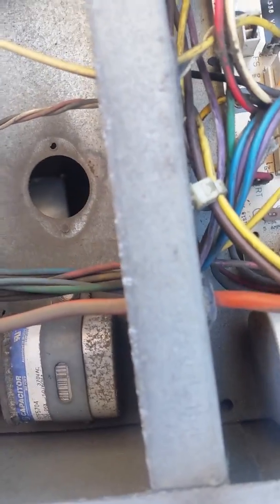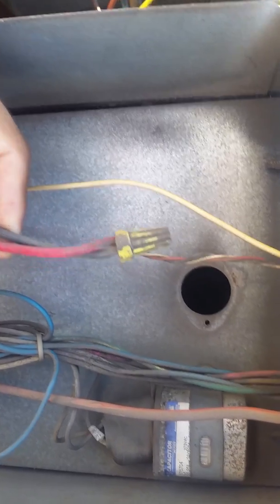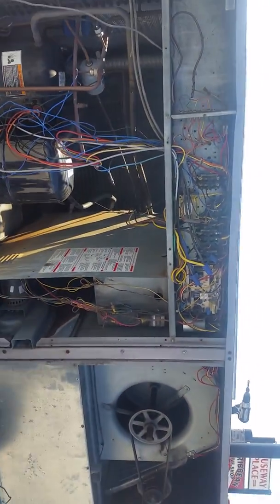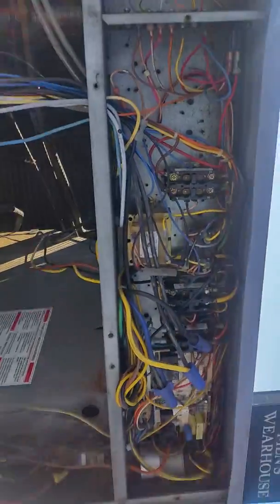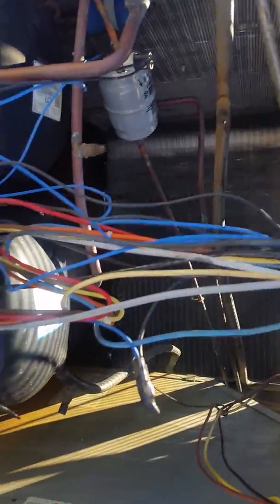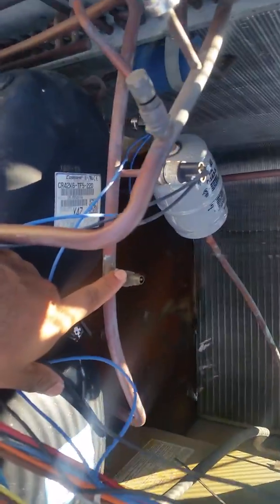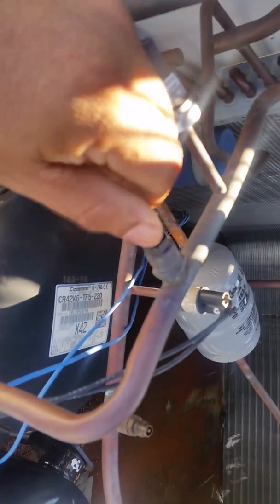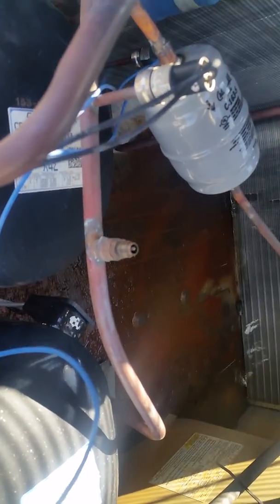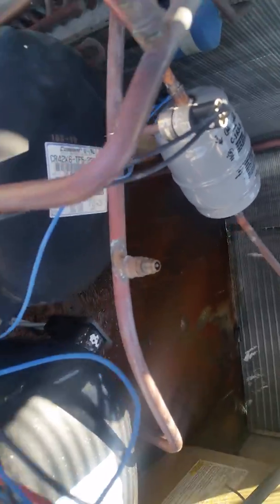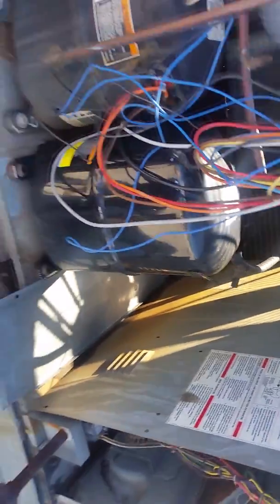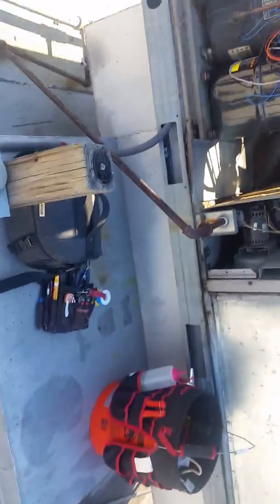As you can see, some components have been bypassed. Right here we have what is called a flame rollout sensor. Somebody bypassed it. That's a no-no, always a no-no. So the unit has been poorly maintained. Just overall, they could have done a better job. They don't have any refrigerant caps. That's to prevent the refrigerant from leaking out, just like an air tire, a Schrader core valve. So I'm going to be looking at the ductwork here shortly.